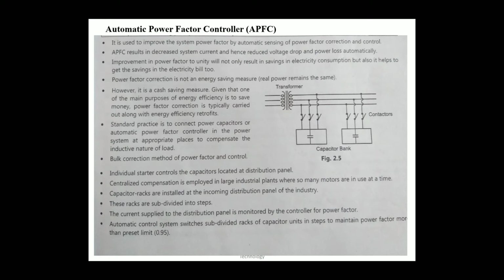Bulk correction method of power factor and control. Individual starter control of the capacitor located at the distribution panel. Centralized compensation is used in large industrial plants where many motors are in use at a time. Capacitor racks are installed at the incoming distribution panel of the industry. These racks are subdivided into steps.